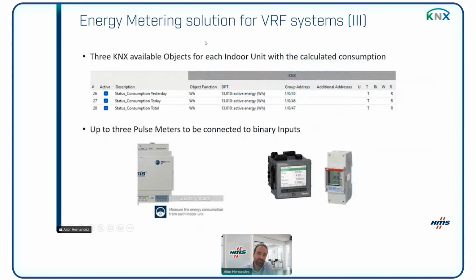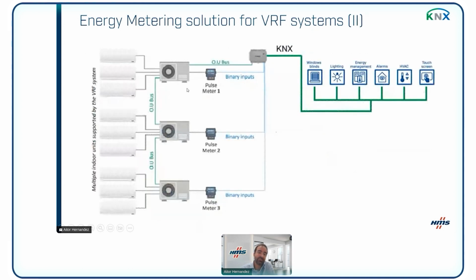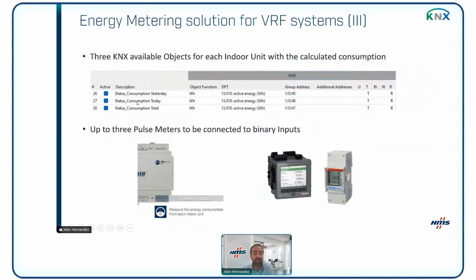This is the result: we create a signal for each indoor unit with the consumption yesterday, today, and the total accumulated. This consumption is obtained according to these values here. As I said, up to 3 pulse meters can be connected to binary inputs. We can also use Modbus TCP meters instead of pulse meters, depending on the installation, the topology, and so on.